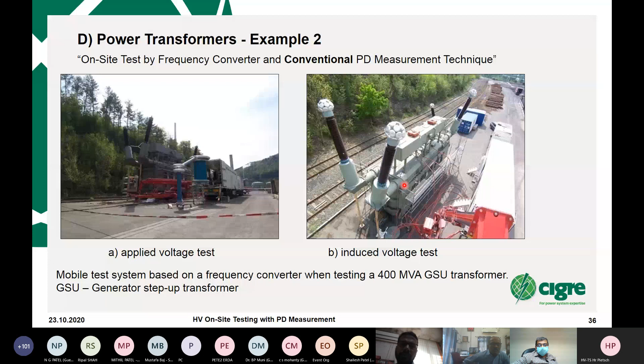So in this case, it was with a resonant frequency, and could be maybe also 50 Hertz, I'm not quite sure. And here you see the coupling capacitor, as I said, was done with a conventional method. The other situation was induced voltage. So we use the low voltage part and feed it with a power source, and then the transformer is stressed, not perfectly the same way as it really is with a high voltage. Inside there are slight differences, but nevertheless, this gives a lot of information about the behavior of this transformer after a repair. For example, if the bushings had some problem and were exchanged, then you will definitely see what is going on, even if you don't have the possibility to do it like this with the applied voltage test. So in this case, both things were possible.